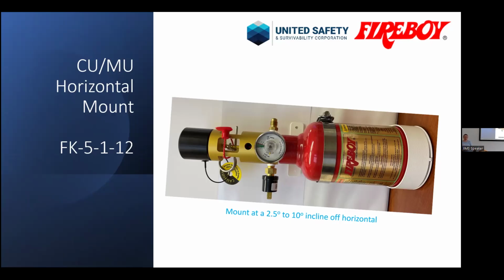Now, this should have been checked on a commissioning before the vessel leaves the shipyard, but if it's a refit or replacement after end of the life, you could come across an incorrect installation. The cylinder will still discharge, it will still work, the chemical will come out, it's just the concentration might not be 100% enough to put out the fire if it's not mounted as per manufacturer's instructions.